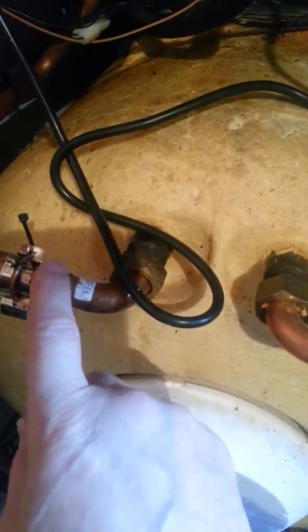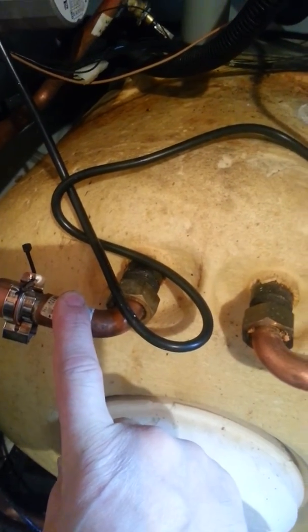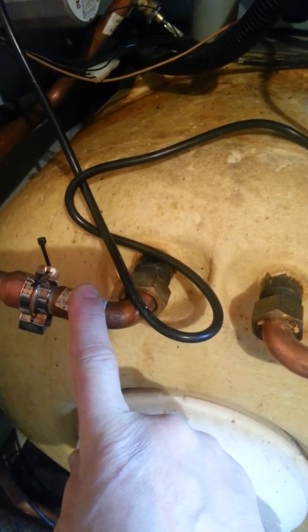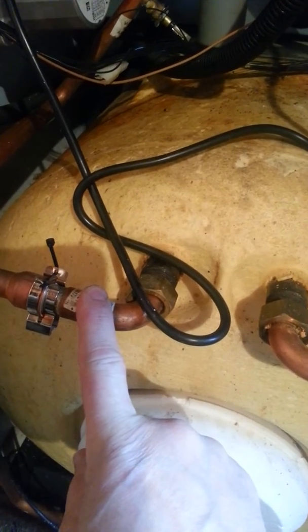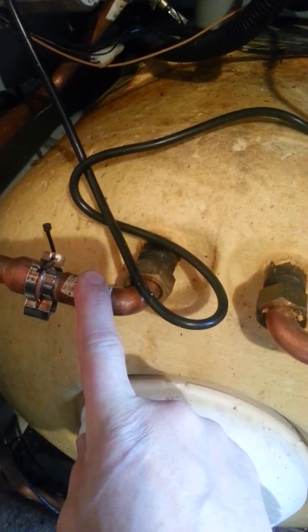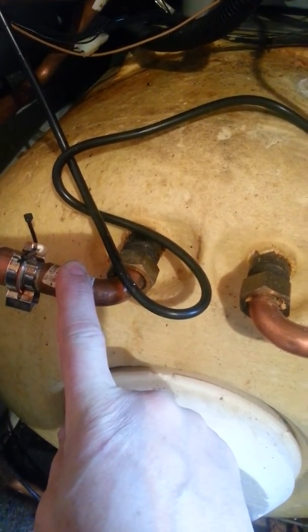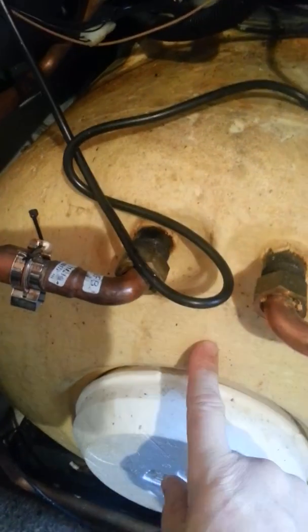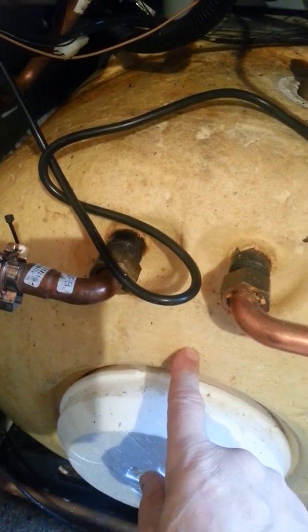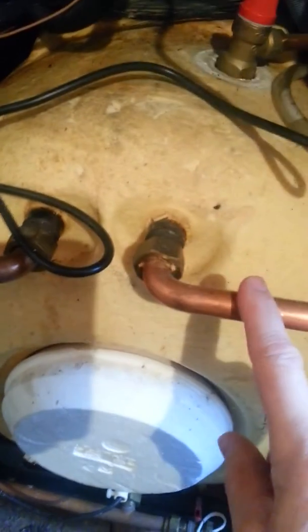So you've almost instantly got your, I don't know, something, I think it's a 26 kilowatt, so probably providing something in the region of about 9 litres or so at 35 degrees rise. So you've got that water combining with the pre-stored water at about 50 degrees in the cylinder being drawn off here.